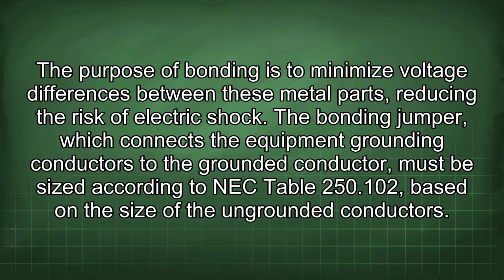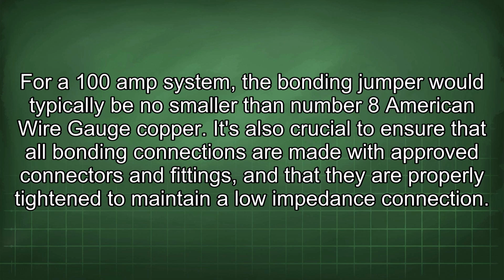The bonding jumper, which connects the equipment grounding conductors to the grounded conductor, must be sized according to NEC Table 250.102, based on the size of the ungrounded conductors. For a 100 amp system, the bonding jumper would typically be no smaller than number 8 American wire gauge copper. It's also crucial to ensure that all bonding connections are made with approved connectors and fittings, and that they are properly tightened to maintain a low impedance connection.